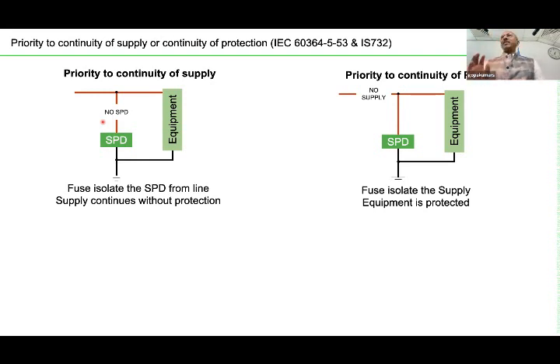This is a very important subject. For example, not in normal life, let's say you are designing a wind turbine. You know the size of the wind turbine, and probably you must have seen a wind turbine. In a wind turbine, you want to protect its electronics. Which one will you prefer? The first one, priority to continuity of supply, or priority to protection? Priority to protection. Because in the first case, priority to continuity of supply, there is no SPD.